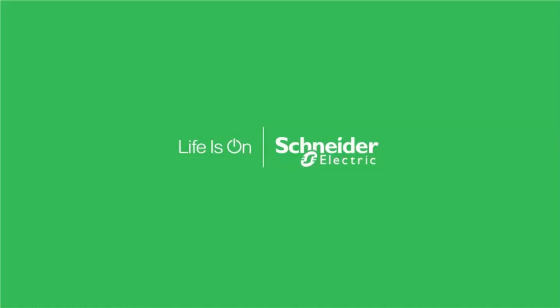And so major changes, if you've had a facility and you've, for example, added a standby generator to make sure that you can ride through ice storms or hurricanes or whatever the case may be. If you have equipment now that's fed from generator, the labels that you have on your equipment from when it's fed from utility are no longer valid for that case. It's two different sources. That would be a great example of one where you need to look at that, or certainly adding equipment, you would need to look at those.